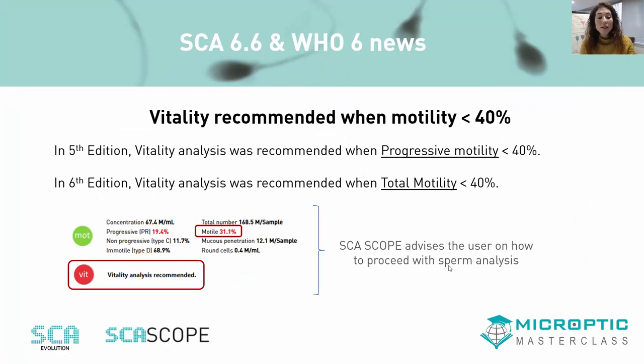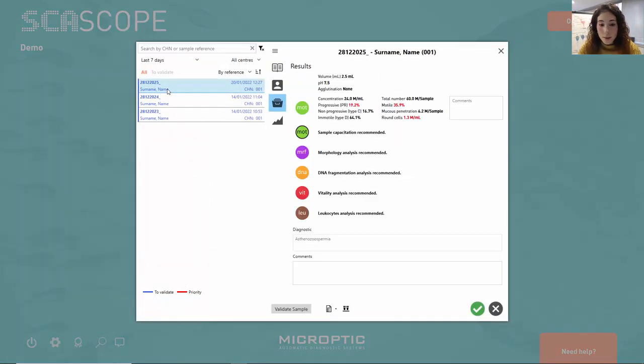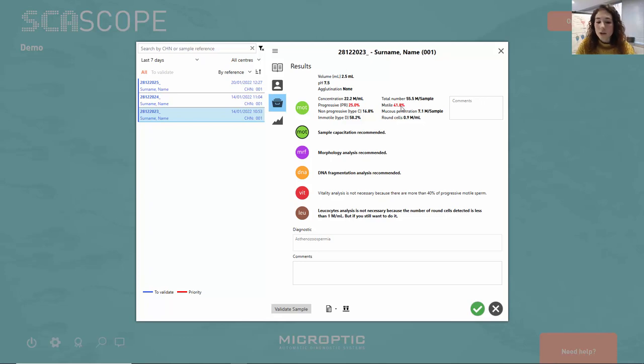Moving on to the next item: vitality assessment is now recommended when total motility is less than 40%. In the 5th edition, vitality was recommended when progressive motility was under 40%, but now it is the total motility. In the SCA Scope, for example, if we search for a sample and the motility was under 40%, the vitality analysis is recommended. With another sample where motility is higher than 40%, vitality is not necessary. These settings in the Scope can provide the technician with guidelines on how to proceed with the semen analysis.